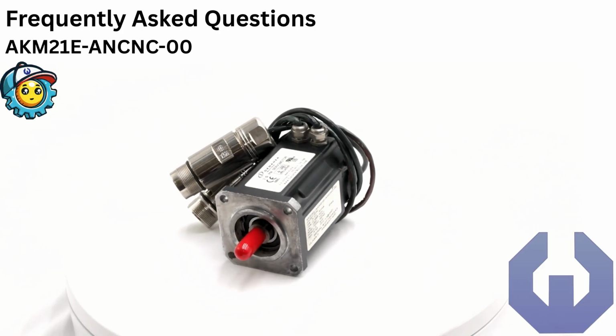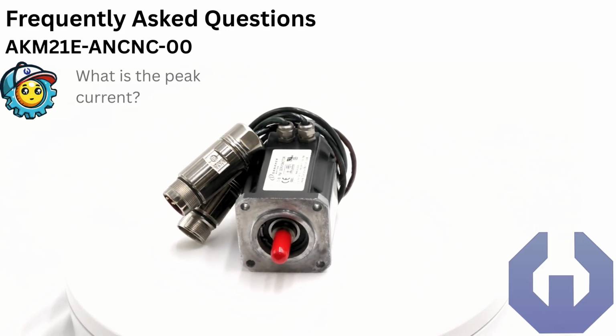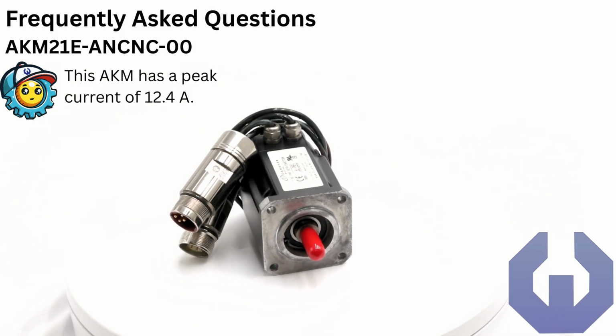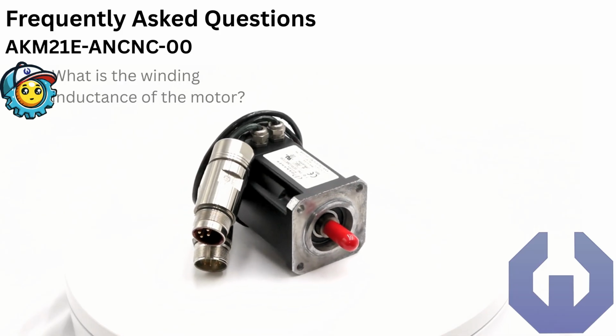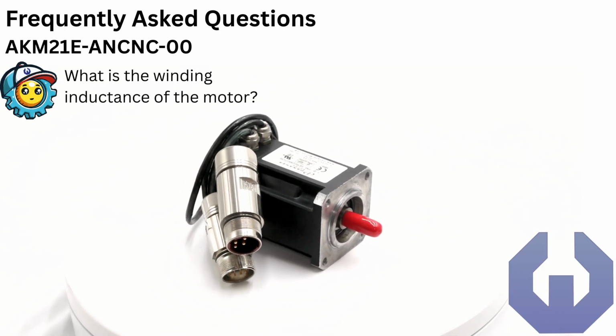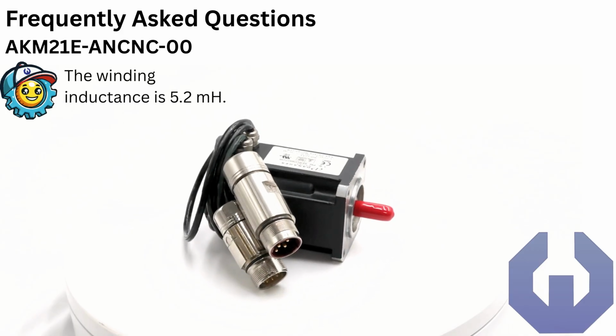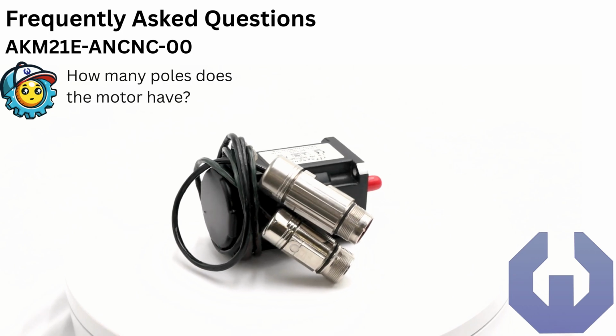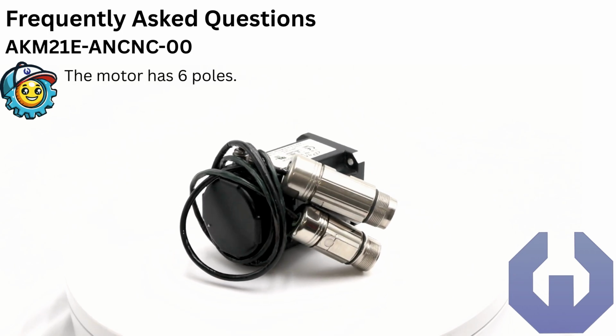Frequently asked questions. What is the peak current? This AKM has a peak current of 12.4 amps. What is the winding inductance of the motor? The winding inductance is 5.2 mH. How many poles does the motor have? The motor has 6 poles.